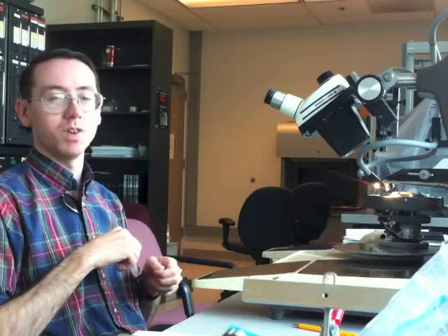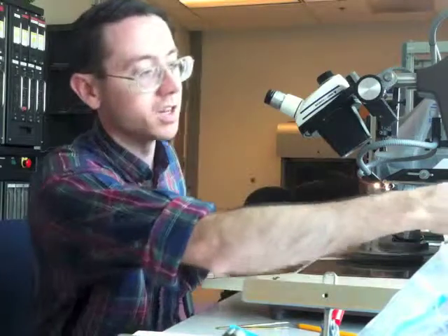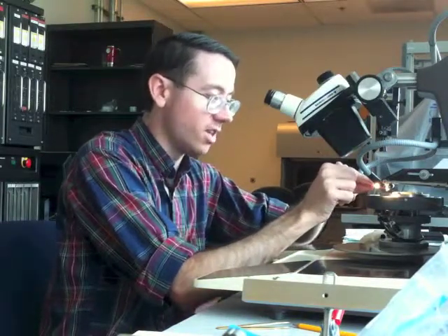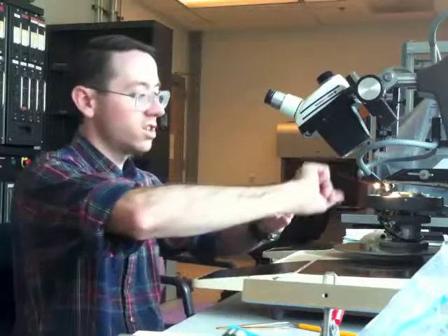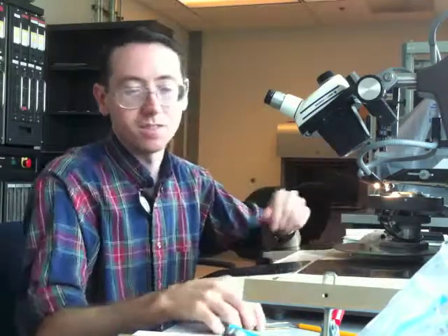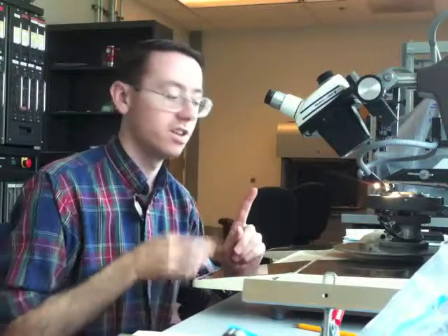You'll also have times when the needle gets completely clogged. I have been able to successfully un-clog needles. What you do is take the needle out — there's a little wrench that releases the allen screw right in the front of that arm. You unscrew that, the needle comes down. Then you turn the needle around, hold it back up under the microscope, and you can see the tip. You can often see the clog, and sometimes just scraping on the outside like that can remove the clog — it's actually not in there very hard.